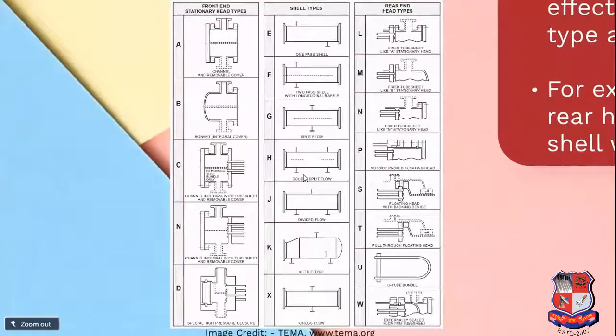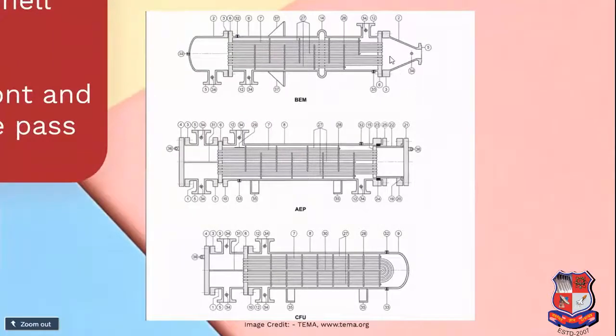Here you can see the BEM type of heat exchanger. And also I would like to inform you, here there are again different numbers attached with the different parts or components of a heat exchanger. Those missing numbers in previous diagrams you might find over here, because each heat exchanger has different components. Here you will be seeing a 37. This is a bracket support. This number 14 is an expansion joint. Again, this type of head is a conical head. So every heat exchanger comes with different components. Now this heat exchanger is named as BEM.